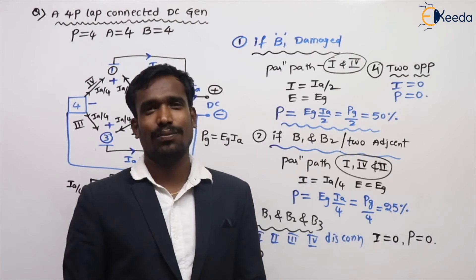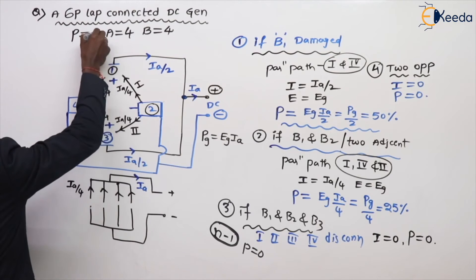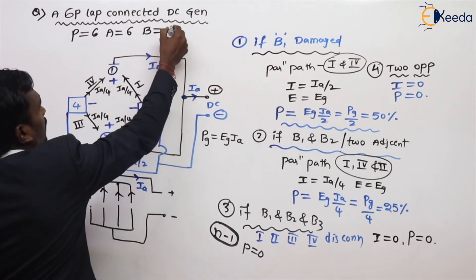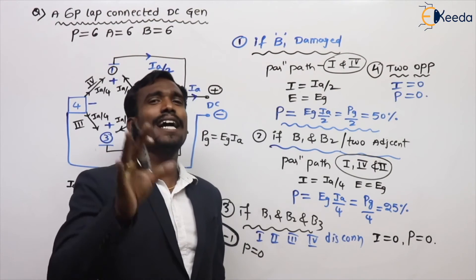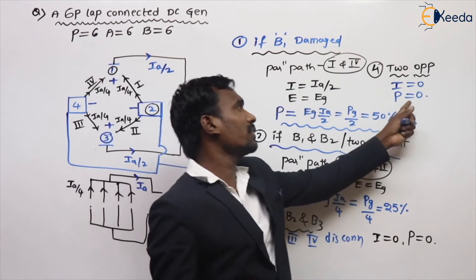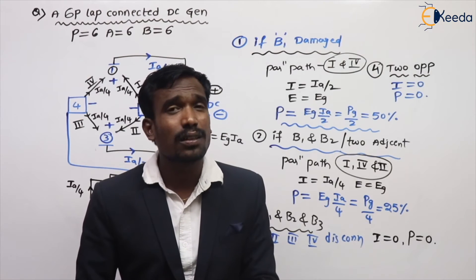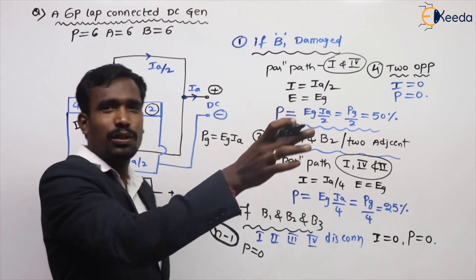Now analyze the same thing for a six-pole machine. For a six-pole machine: number of poles is 6, number of parallel paths is 6, and number of brushes is 6. You will analyze cases: if brush 1 damaged, 2 adjacent brushes damaged, 3 adjacent, 4 adjacent, and 5 adjacent — only five cases. The special opposite-brush case is not possible for other machines; only for the four-pole machine. Also, for wave winding: if any one brush is damaged, the power developed is 0, because wave winding has only 2 brushes.